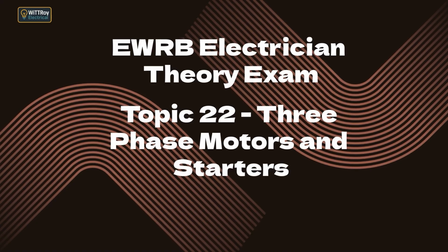Topic 22.2h. Explain the effect of load on an induction motor's PF and efficiency. As load increases, power factor improves, moves closer to unity. Efficiency increases up to a point. At very light load, both PF and efficiency are poor. Induction motors operate best near their rated load.